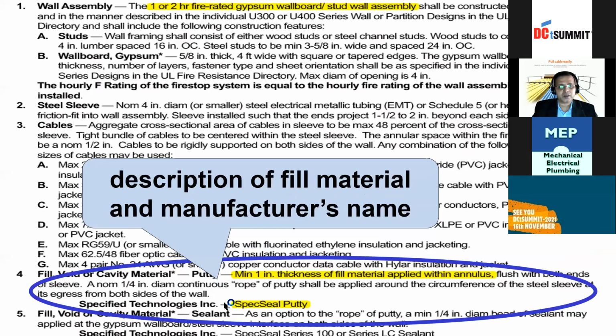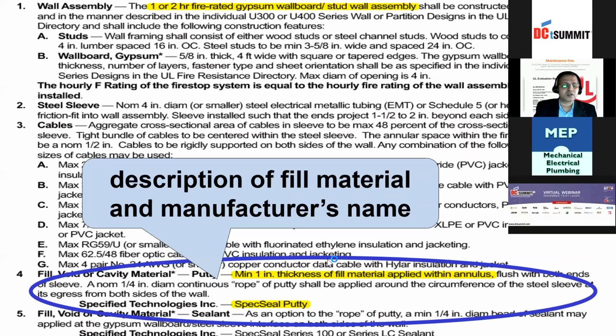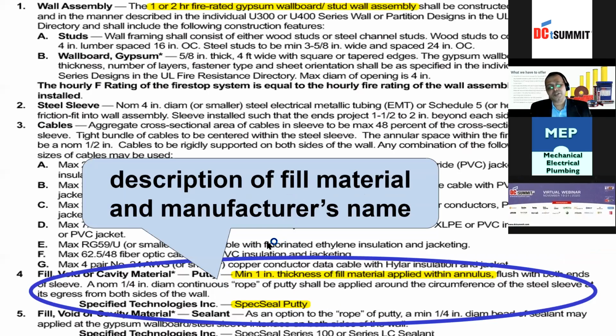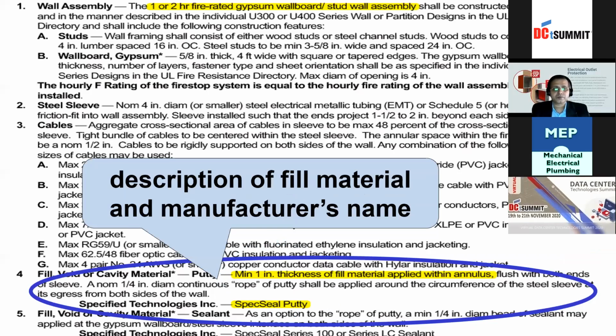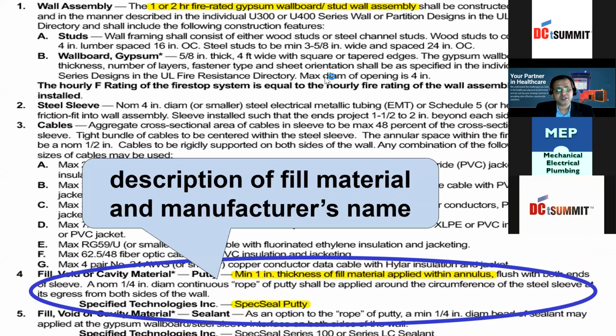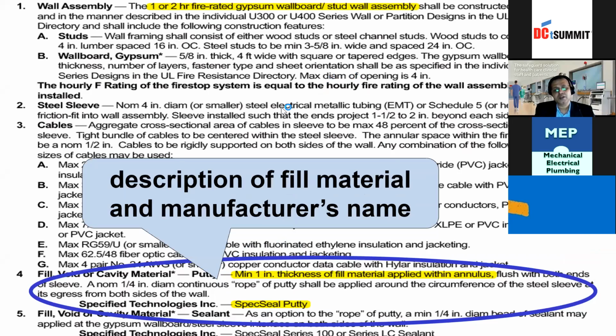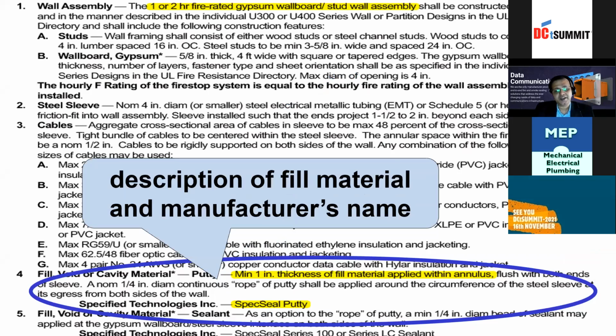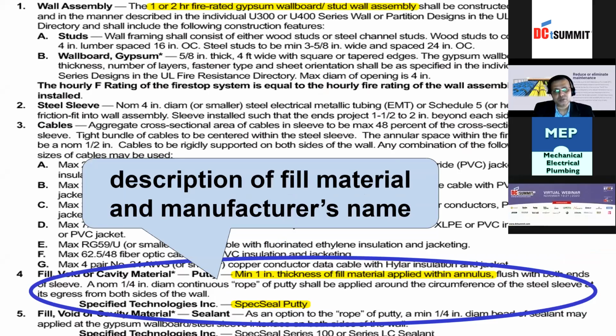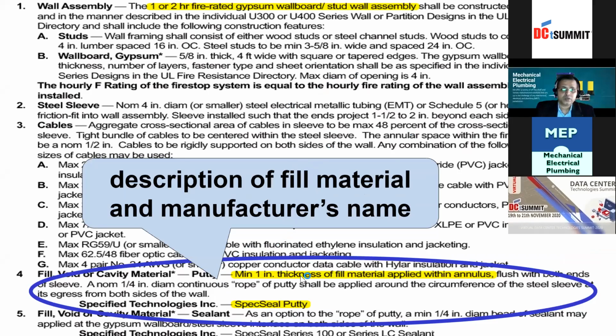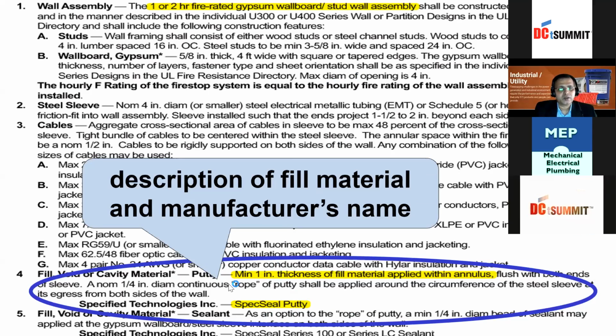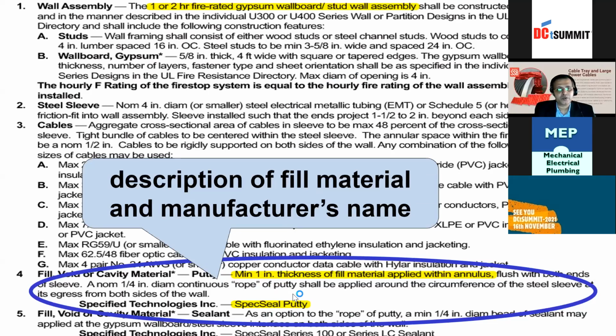Any installer or any MEP consultant should look into this, because end of the day, it doesn't matter which product you are buying, but if you have a UL tested system to support your project, 99% of your problems is solved. Because if someone comes and asks you what is the backing material to be used, you don't have a say. Here it's very clearly mentioned, there is no backing material. It's just seal it, the putty has to be installed directly.